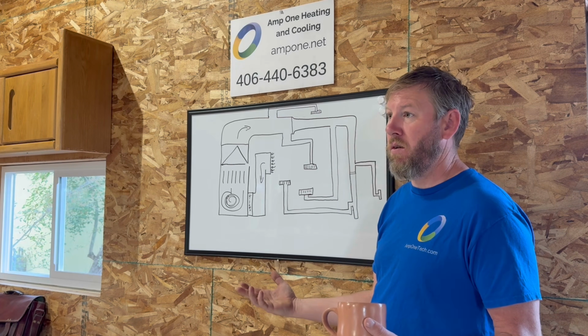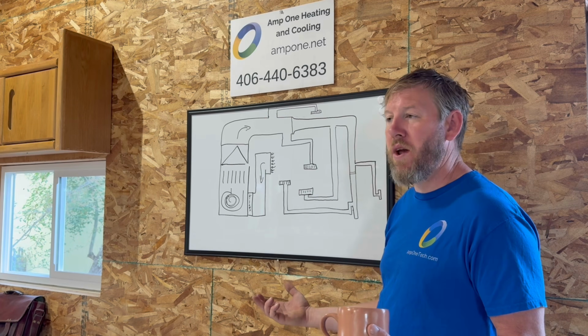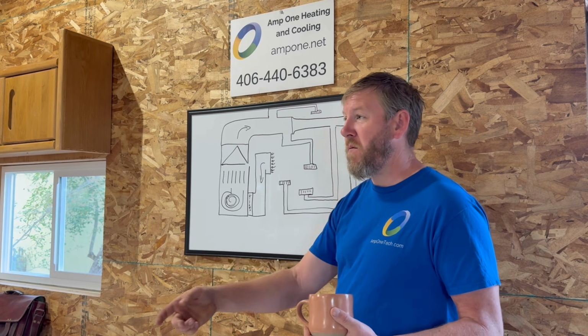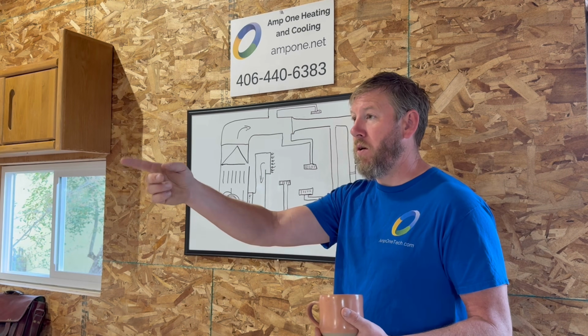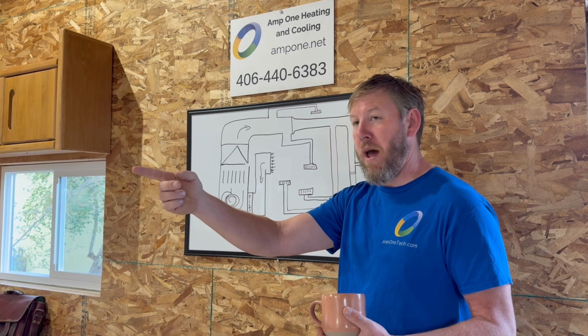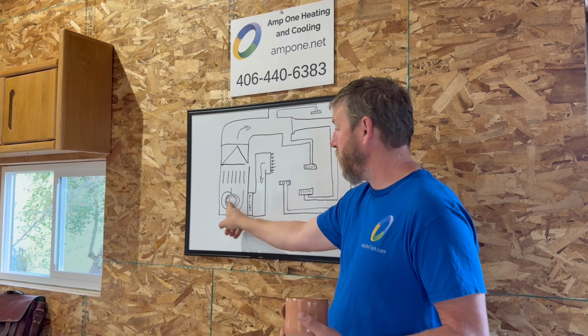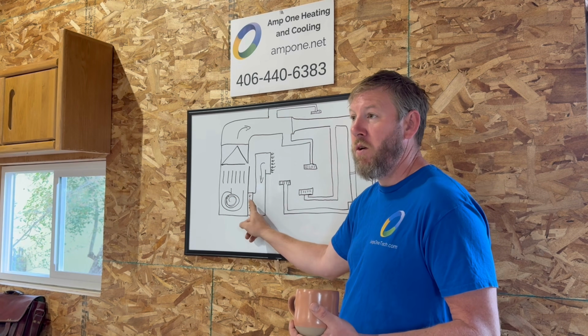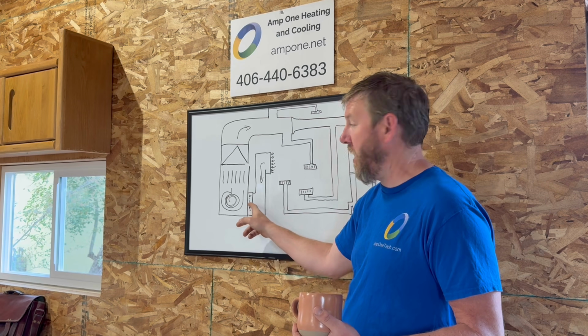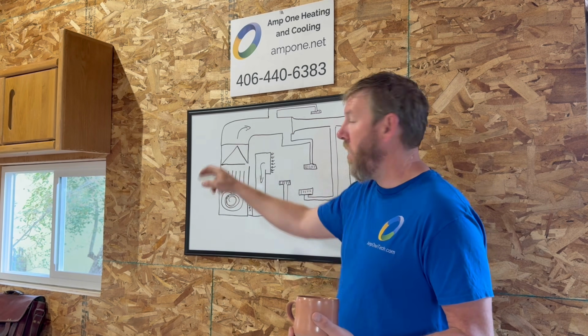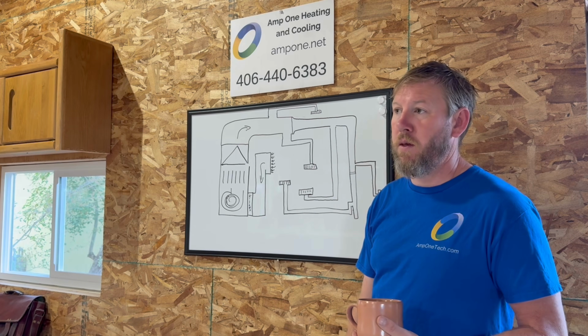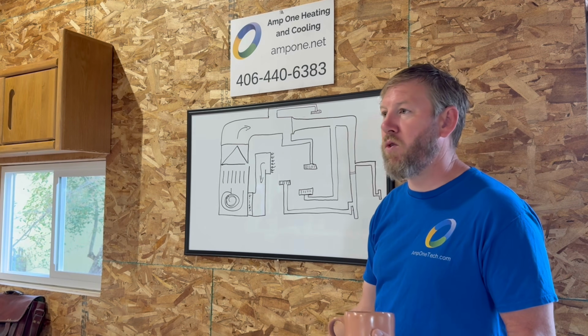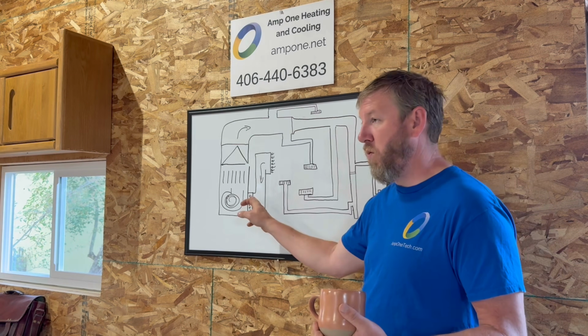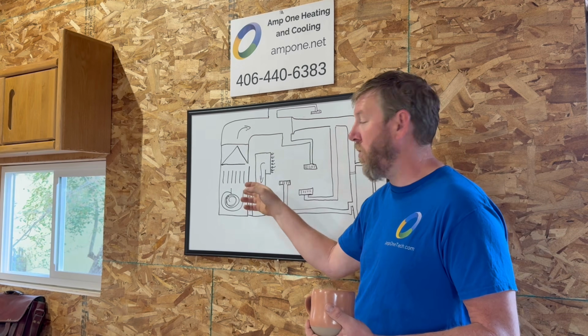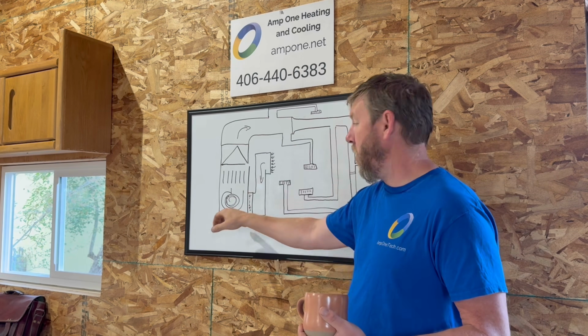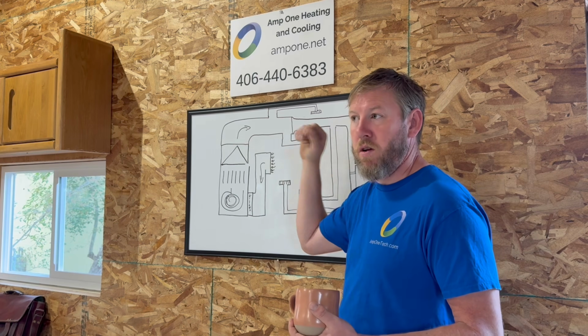Slows that airflow down. Usually not crazy amounts, but let's say like what happened at a gal's house with a slightly bad capacitor. Her fan wasn't running up to speed. She had a 14 MERV filter where it was designed for an 8, and it was just slowing it down, and the coil kept freezing up. Oh. And everything seemed like it was working fine, but if we ran that test, we would have found something's going on. We're not getting enough airflow across this thing.